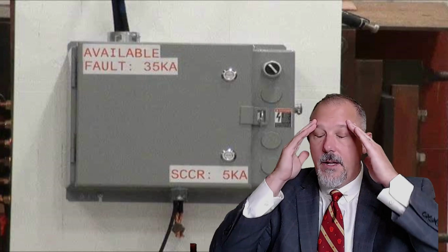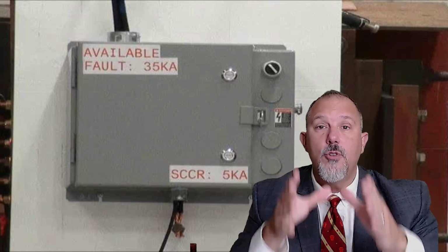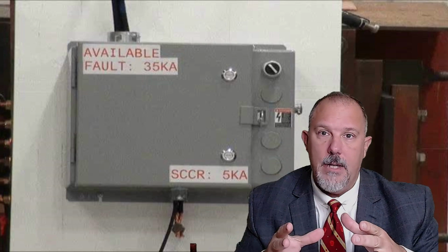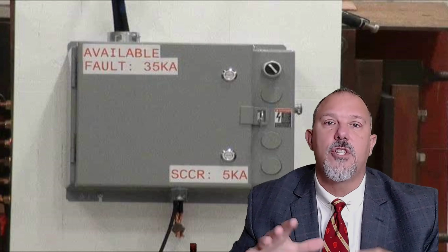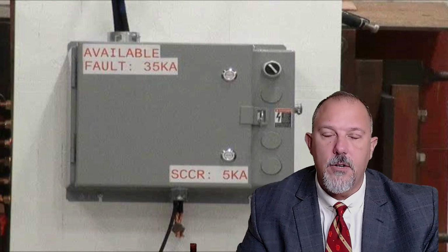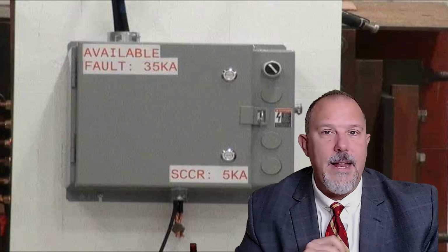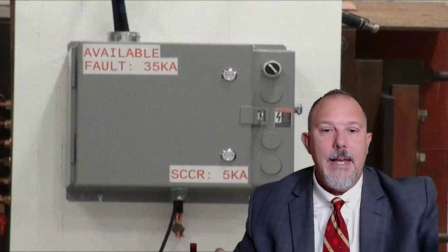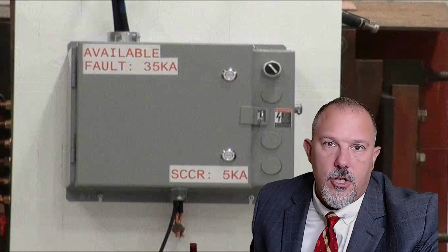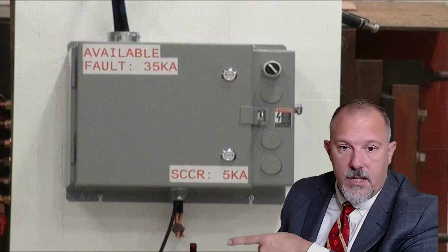Now, I just want to help you understand. Short circuit current rating is not the ability of a device to stop the flow of current. Circuit breakers and fuses do not have a short circuit current rating. Equipment has a short circuit current rating. You see this right here?